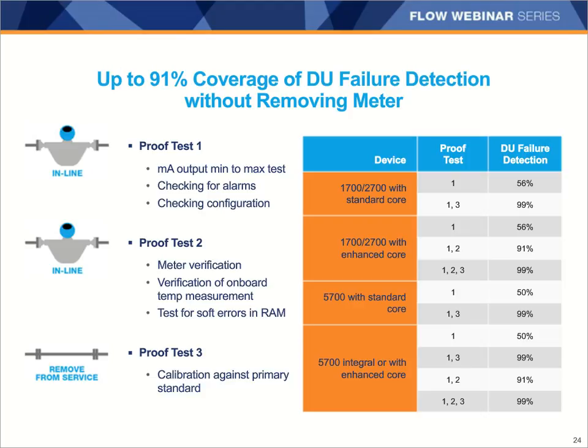So the table here shows the results of the DU coverage of the various transmitters with different types of proof testing. And as you can see, the first 2 proof test options allow you to leave the meter in the line, so you have minimal disruption. And then the third proof test is a full proof test where you pull the meter from the line. The first proof test option checks the milliamp output, the alarms, and the configuration, and covers about half of the undetected failures. You might notice actually the 5700 transmitter has a lower DU failure detection coverage in this method than the 1700 or 2700.